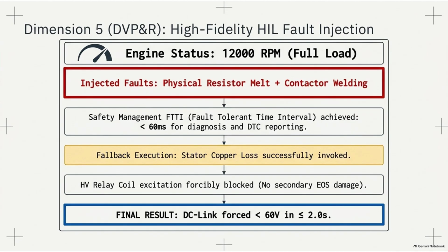What is the computer expected to do with that nightmare? It has to prove its ultimate autonomous intelligence. Within exactly 60 milliseconds of that digital chaos being injected, the safety management unit must process the data, recognize that the voltage isn't dropping, deduce that the physical resistor is broken, instantly pivot its strategy, abandon the primary discharge plan, and trigger the stator copper loss backup plan.